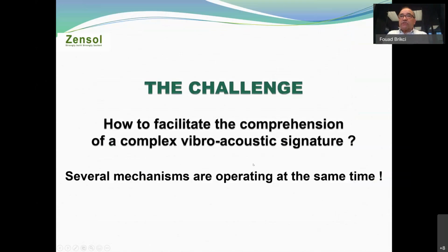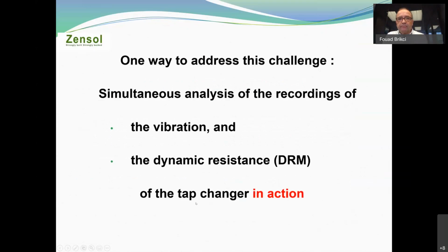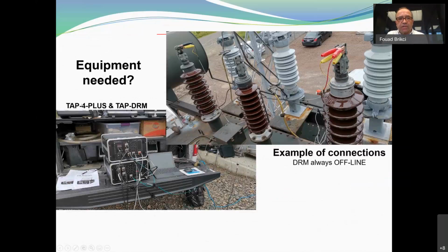Now the challenge: when we only have the vibration, you are able to listen, but not able to correlate the vibration with what happens in the tap changer. So the challenge is how to facilitate the comprehension of a complex vibroacoustic signature, because several mechanisms operate at the same time. One way to address this is to analyze simultaneously the recording of the vibration and what we call the dynamic resistance, DRM, when the tap changer is in action. So what we need is the Tap4 Plus that you can see here, and the Tap DRM accessory.